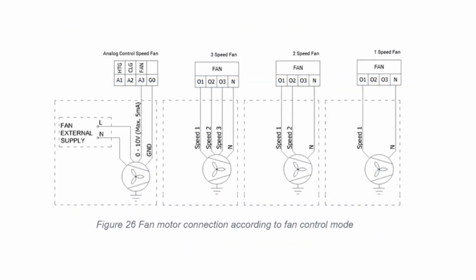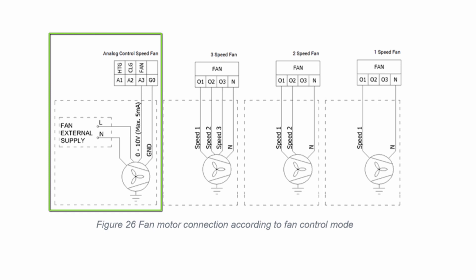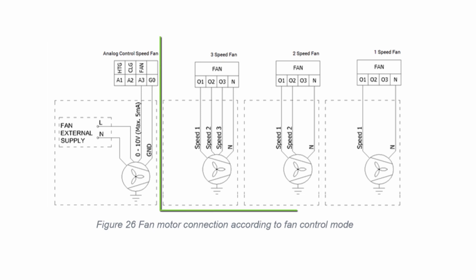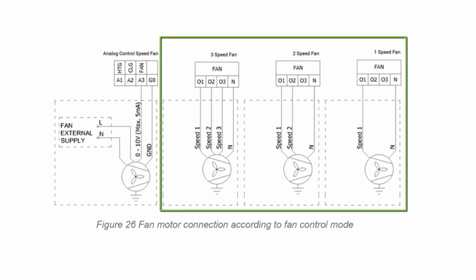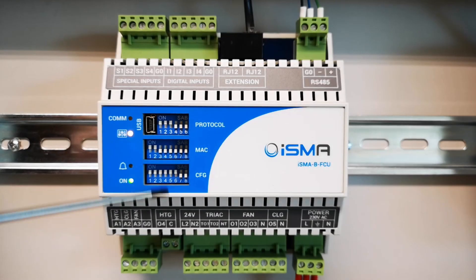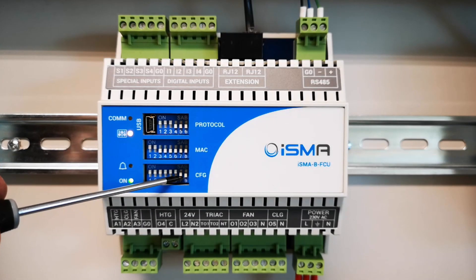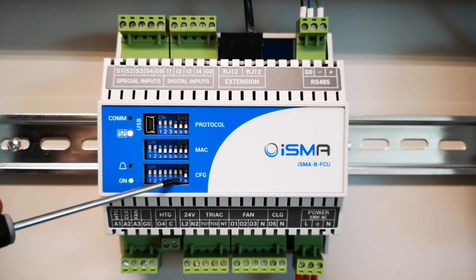The default application is designed to control one of 4 different fan coil unit types: controlled by analog value from 0 to 10V, or 1, 2, or 3-speed fan coil type. Configuration DIP switches number 7 and 8 are reserved for that fan coil unit type control selection.